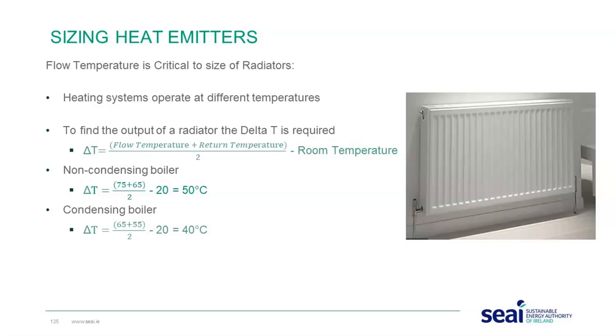Condensing boilers work more efficiently at lower temperatures, specifically when the return temperature is less than the dew point, so they would be run lower. So the delta T would be different when we're looking at a radiator for a condensing boiler than for a non-condensing boiler. An example here: 65 flow, 55 return, less 20 degree room temperature, gives a delta T of 40. Now, in the case of a typical wet heat pump system, as we've seen from the graph earlier, the lower the flow temperature, the higher the efficiency of the unit. So by design, it's natural that we will try to design with as low a flow temperature as possible. In this example, 45 flow, 35 return, less 20 degrees room temperature, gives a delta T of 20 degrees.